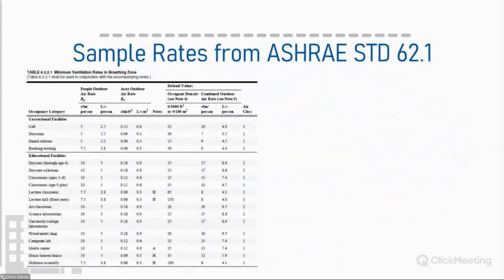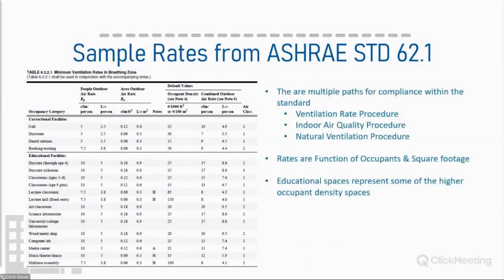So looking specifically at the sample rates for educational spaces, there are 3 paths for compliance within the standard. You have the ventilation rate procedure, the indoor air quality procedure, and the natural ventilation procedure. The one that's most commonly used is the ventilation rate procedure, which is a function of the number of occupants and the square footage. What's fairly unique to educational spaces is they represent some of the higher occupant density spaces, meaning these spaces traditionally have higher ventilation rates associated with them.